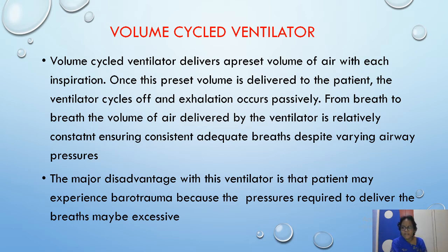The major disadvantage with this ventilator is that the patient may experience barotrauma because the pressures required to deliver the breaths may be excessive. See, because of excessive pressures, the patient may sustain lung injury. That is the only disadvantage of these volume cycle ventilators.